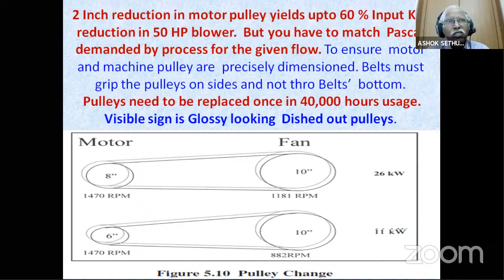This is what we are trying to achieve in the speed ratio of the pulleys. For a given motor, instead of an 8-inch pulley, we replaced it with a 6-inch pulley, a 2-inch reduction in the motor pulley. This gave an energy saving of almost 40% on the driven machine, which was a fan where only that much output was needed.